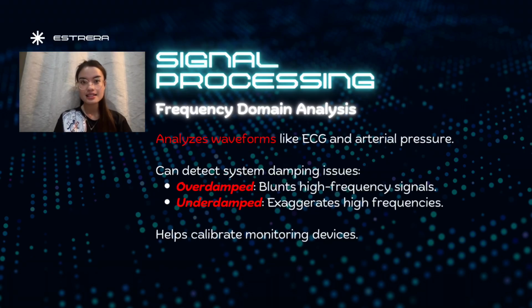By analyzing the signal in the frequency domain, we can spot issues with the monitoring system itself. For instance, overdamping can flatten signals, making systolic blood pressure appear lower than it really is. Underdamping does the opposite. Recognizing these helps in calibrating devices properly.